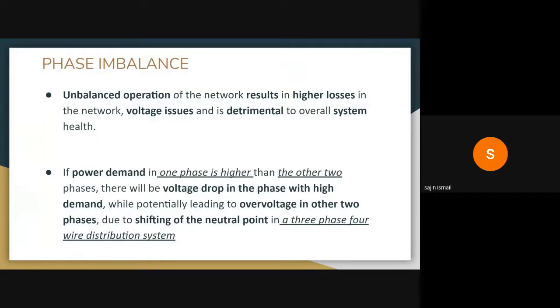From power system understanding, we know that when there is this much imbalance, there will be neutral point shifting. Over voltage in one or two phases and under voltage in another will create enormous issues, which can even affect household equipment meant to work at a lower voltage - higher voltage can damage the equipment.